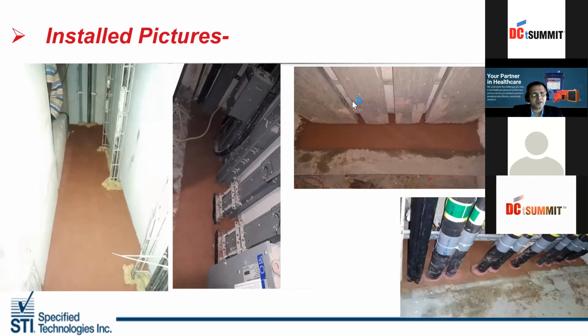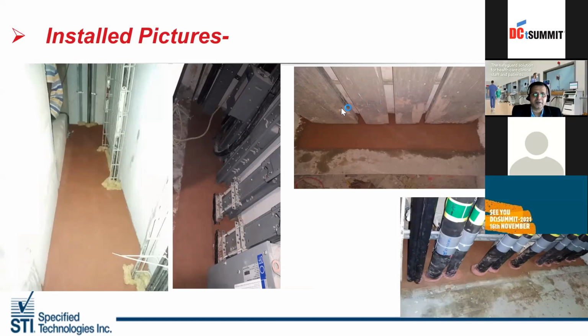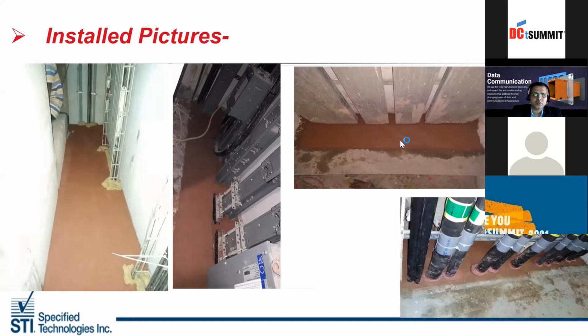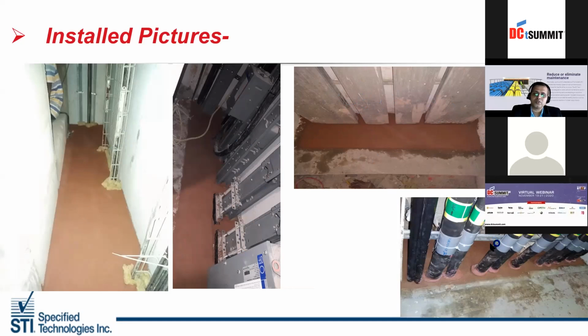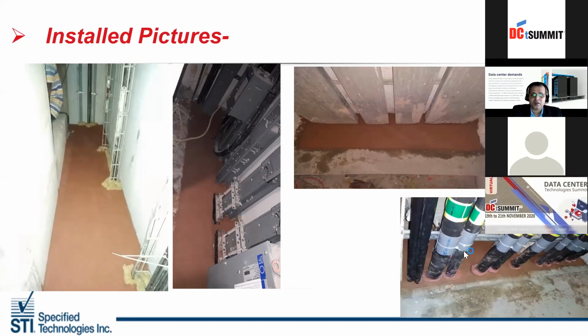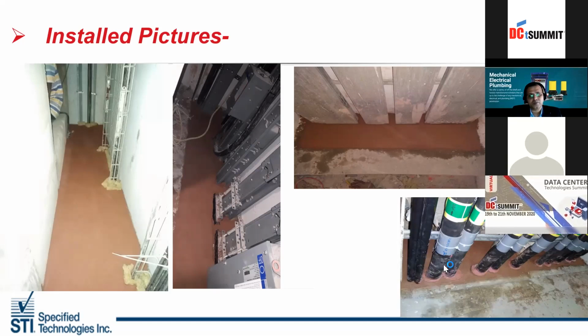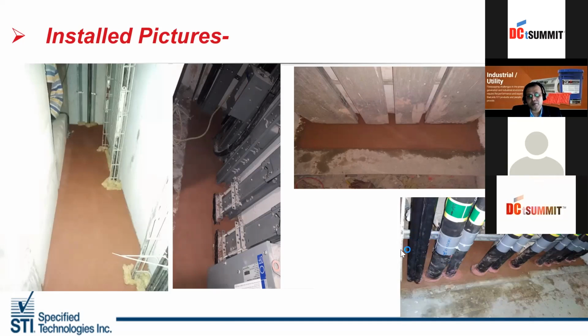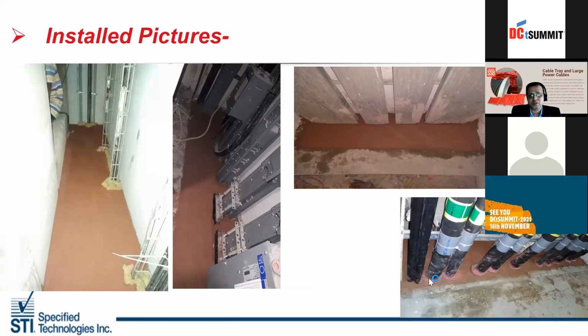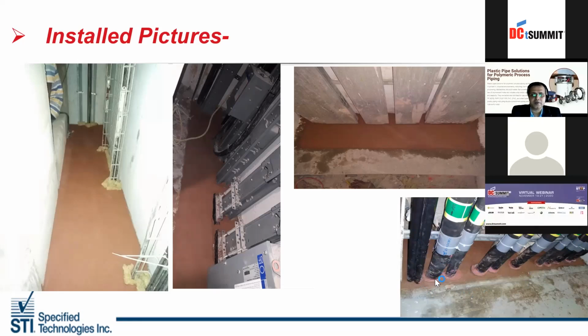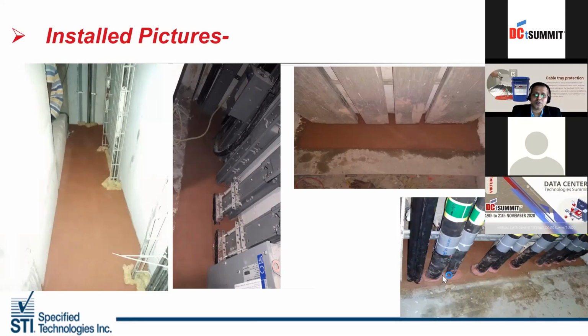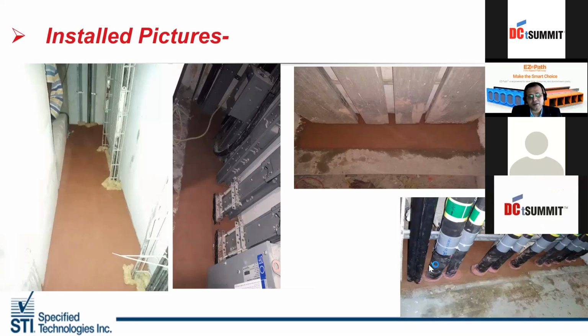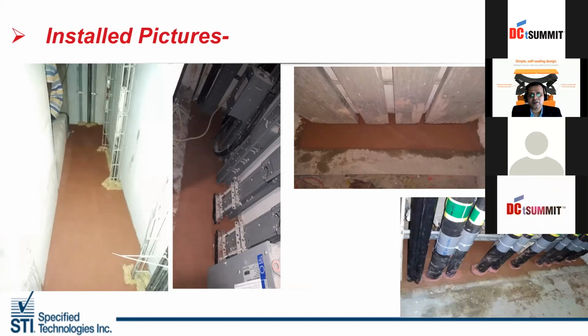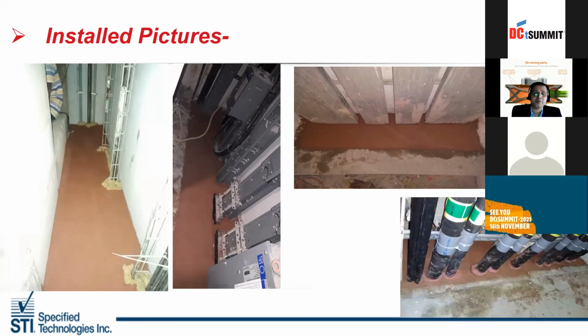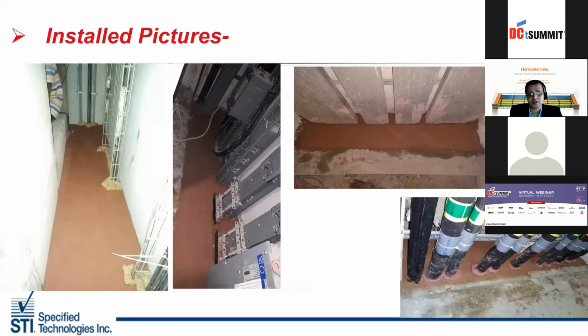Towards your right hand side top, again, it's a concealed metallic cable tray. One single product has been used, the mortar. Now towards your right hand side bottom, these are insulated pipes which are passing through the floor. So the single product mortar cannot be used, and we have used an intumescent sealant. You can see the pale pink colored product around the sleeve. There is a sleeve installed, and the sealants are installed in between the sleeve and the penetrants. So wherever there are combinations, the combinations are used where you have metallic pipes or combustible pipes and cable trays.